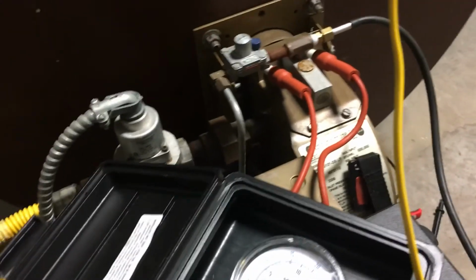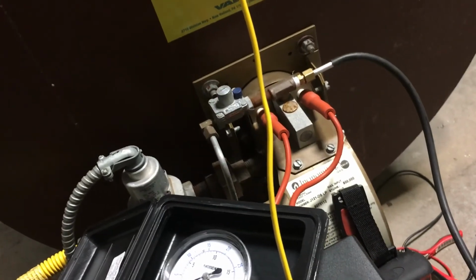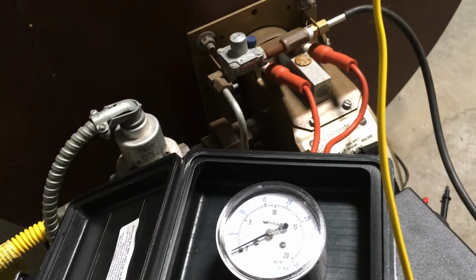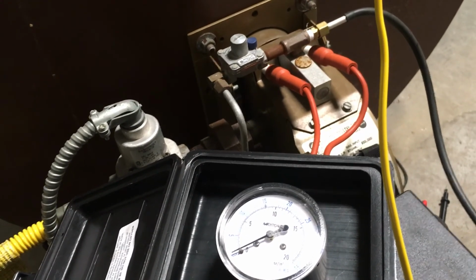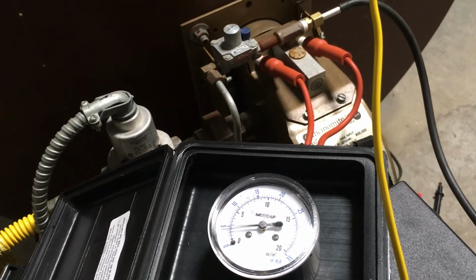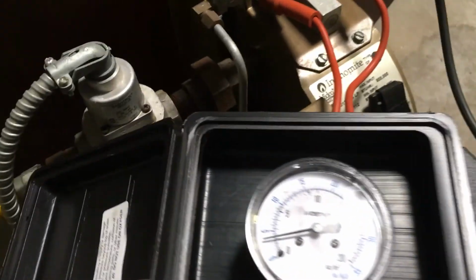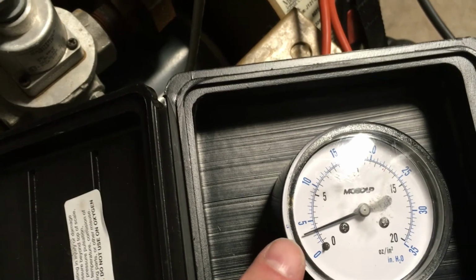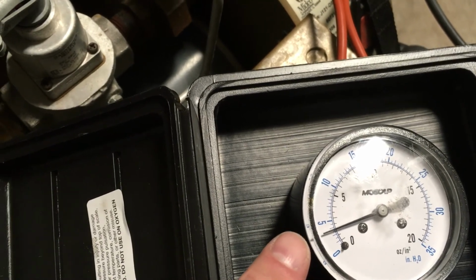So I have my gas valve turned on or open. Running the system. During the 6-second trial period, it should kick in. You can see we're right about where we should be, about 3.5 inches of water column, so we're good.